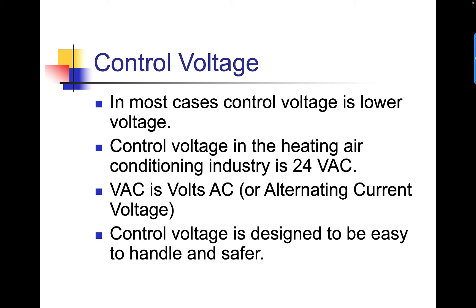Control voltage, in most cases, is lower voltage. Control voltage in the heating and air conditioning industry is 24 VAC. VAC is known as volts AC, or alternating current voltage. Control voltage is designed to be easy to handle and safer.